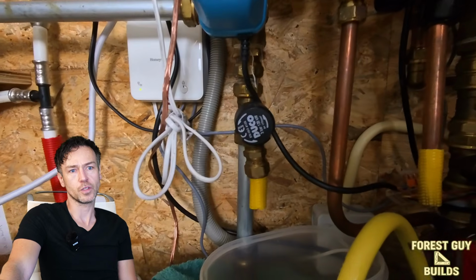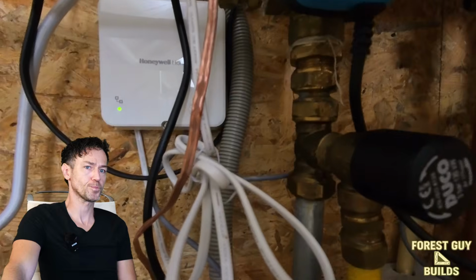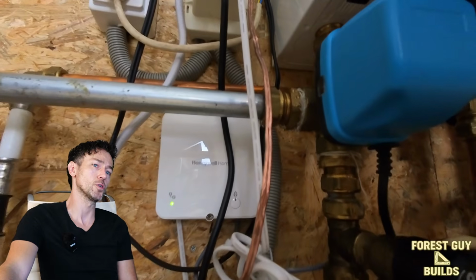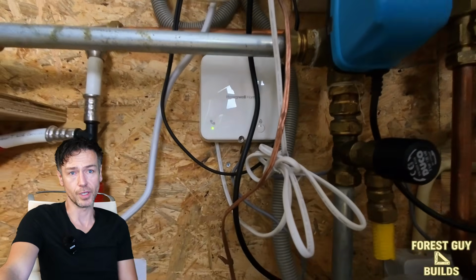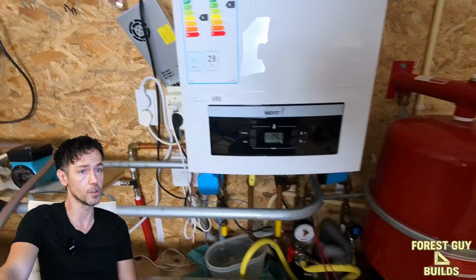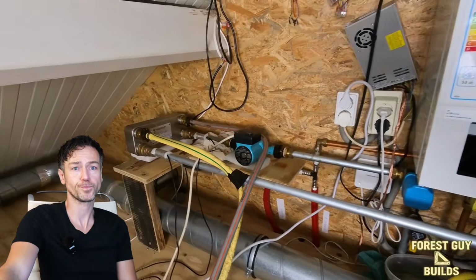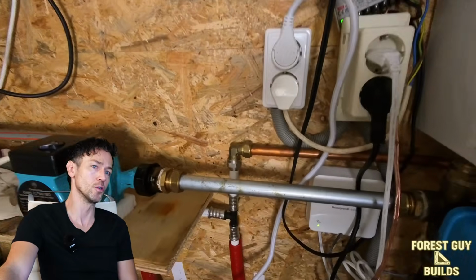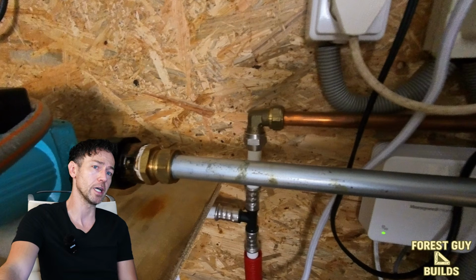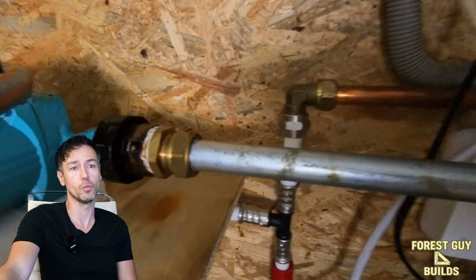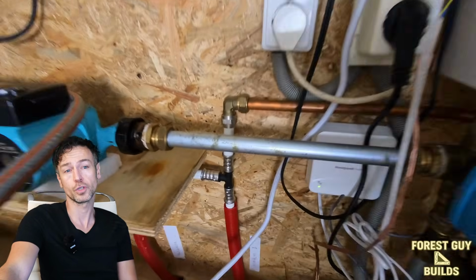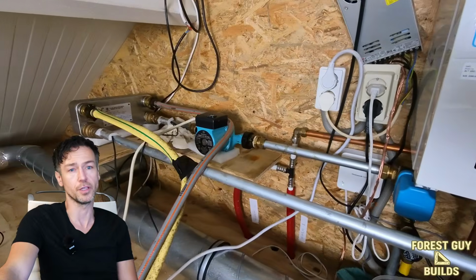After that first test I reduced the groundwater flow, which brought the floor supply temperature up to around 17 to 18 degrees Celsius. It still creates some condensation, but much less than before. So there are two clear improvements to make: insulating these pipes and making the supply temperature more controllable. But for this first prototype test, it's manageable.